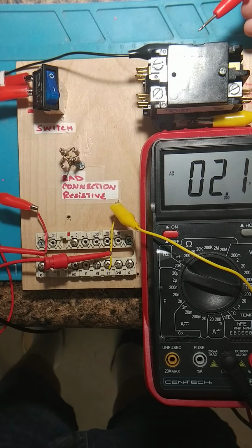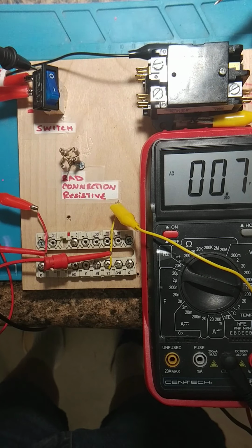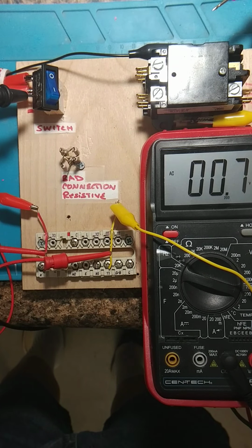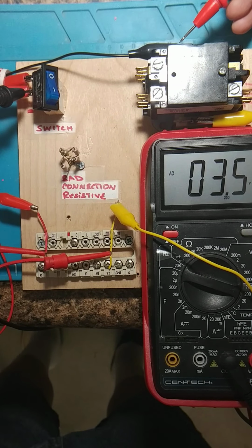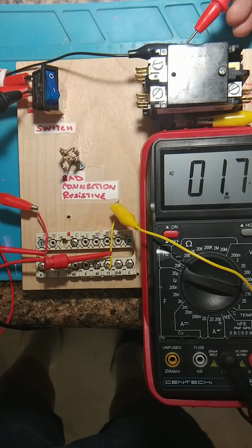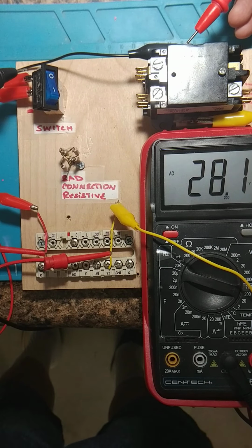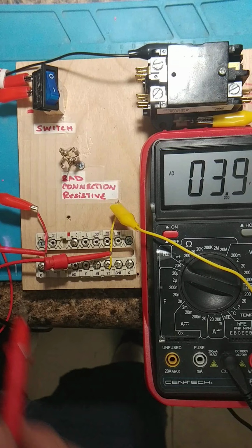So I've got R side of power going to one side of my float, but I don't have it coming out of my float. So if I check between here and common, I've got 0, but if I go to the other side, I have 28. So my open is here.